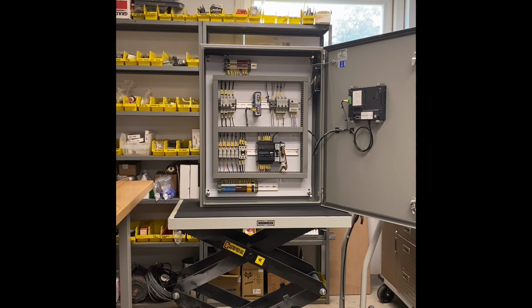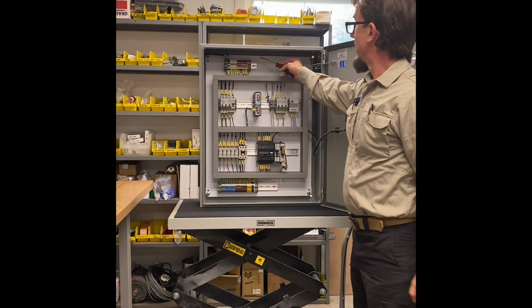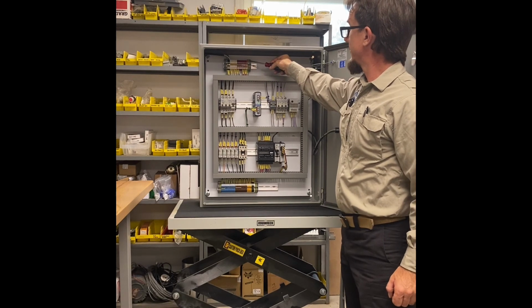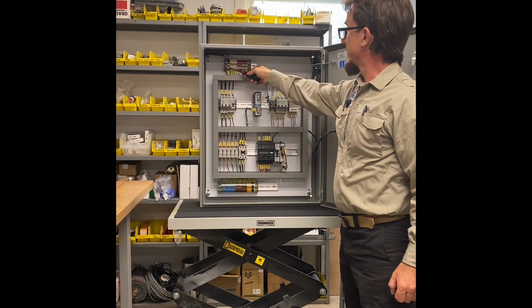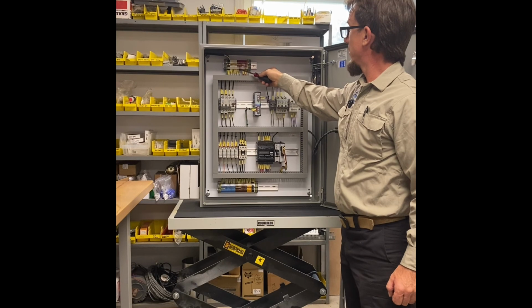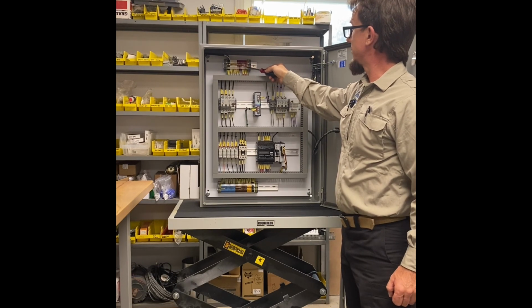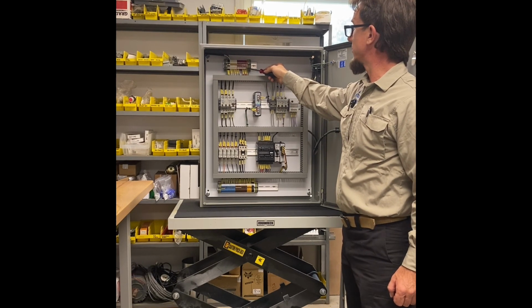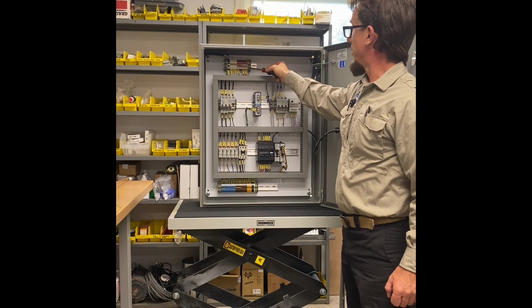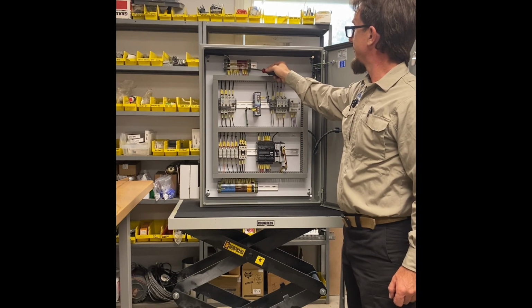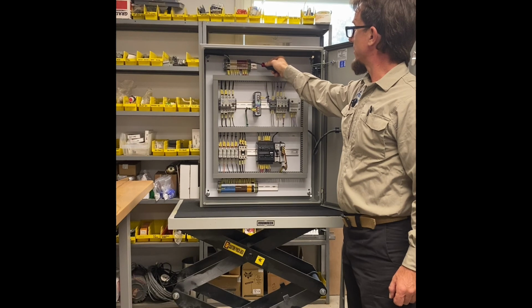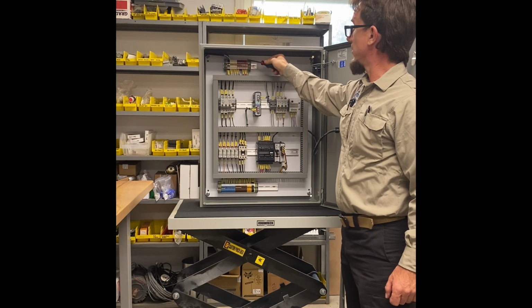So we'll start at the components, we'll walk through them, and I will walk into the camera screen and point each of them out. Our top terminal strip here. I have my incoming voltage, a neutral bar, and these terminal strips are for the low flow pressure switches to verify pumps are indeed putting out water. The orange terminal is strictly for the external alarm light to the building.